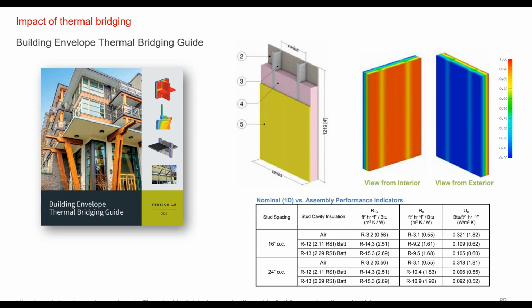And so it's helpful to see they've already done this derating, they've done a lot of testing, and they built what are called these 3D therm models to figure out what is the actual true performance of these different assemblies, depending on whether or not they're thermally broken or they have thermal bridges and things like that. So again, another great resource.